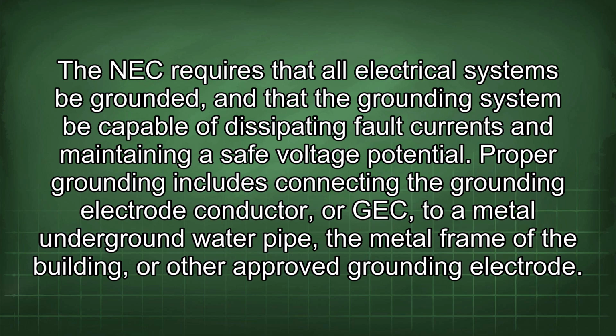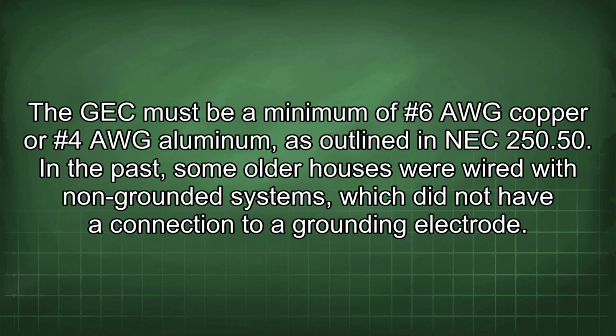Proper grounding includes connecting the grounding electrode conductor, or GEC, to a metal underground water pipe, the metal frame of the building, or other approved grounding electrode. The GEC must be a minimum of #6 AWG copper or #4 AWG aluminum, as outlined in NEC 250.50.